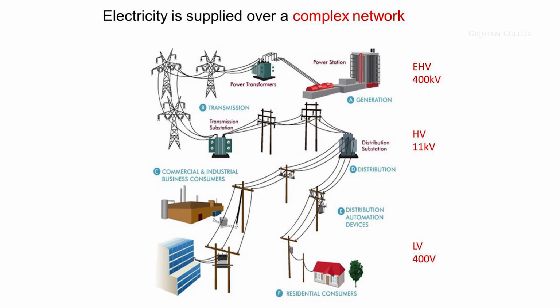The reason electricity is supplied at very high voltage is that the higher the voltage, the lower the current you need to supply a certain amount of power, and electrical power loss is proportional to the current squared. So the lower the current, the lower the loss. So if you have very high voltage, it means there's much lower power loss. The large pylons we see marching over our countryside are operating at this 400 kilovolt voltage, or possibly 100 kilovolts.